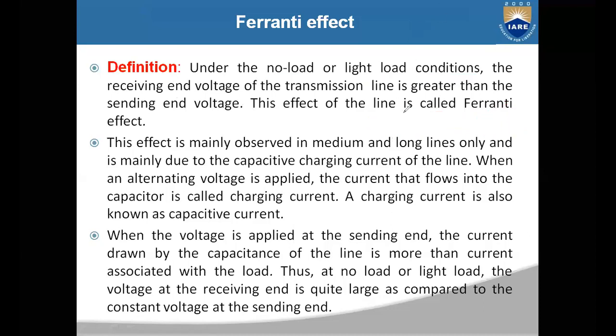Why does this Ferranti effect — where receiving end voltage is greater than sending end voltage — happen? This happens because of the shunt capacitance of the transmission lines. When you consider a long transmission line, there is more shunt capacitance. That shunt capacitance will draw current, called the charging current. When you apply alternating voltage, current flows through the capacitors — the current flowing through those capacitors is called the charging current, also referred to as capacitive current.